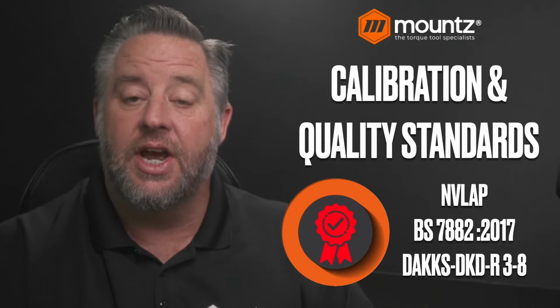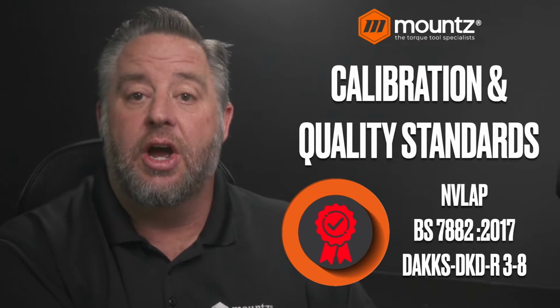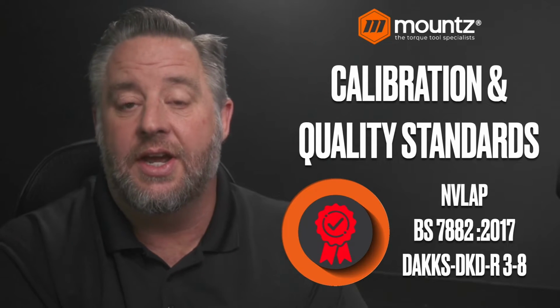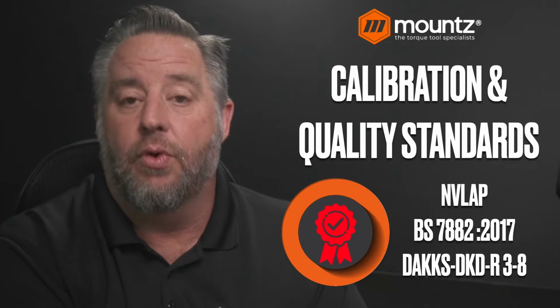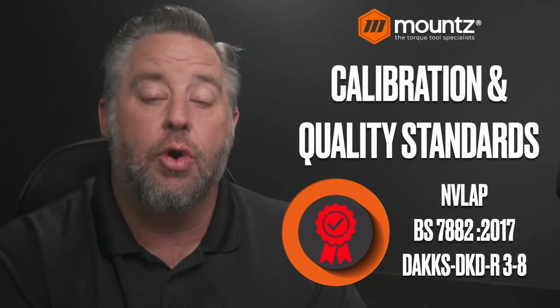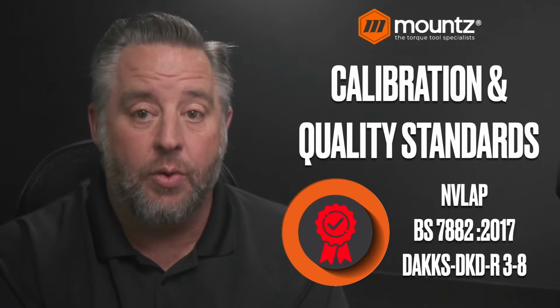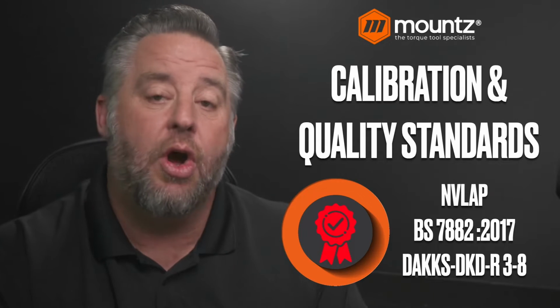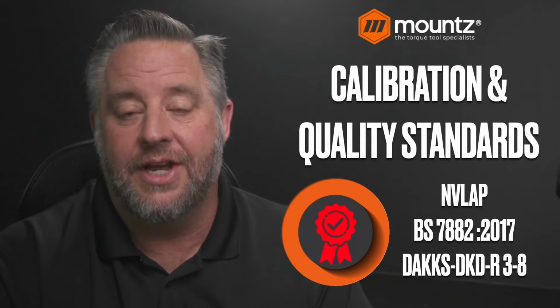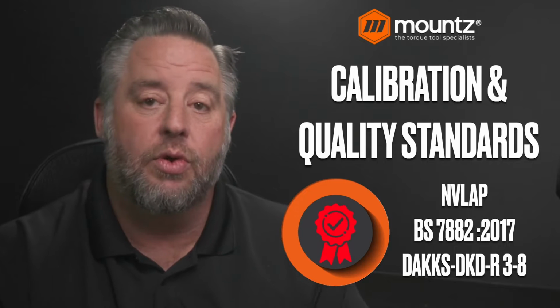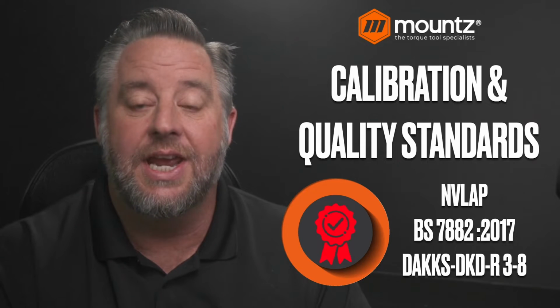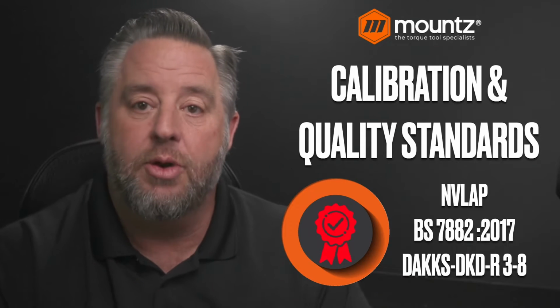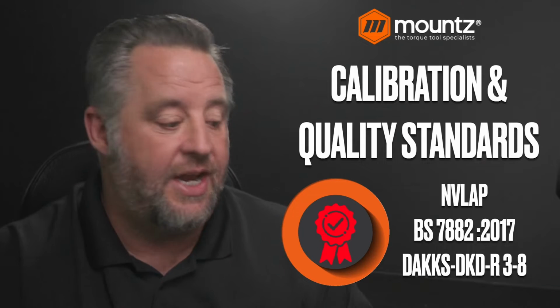In some cases, this may be a 3-point calibration for a torque analyzer, or it might be a 5-point calibration. So it all depends on the standard that's going to be used. And we'll touch on that a little bit as we get into the demo portion of today's presentation.